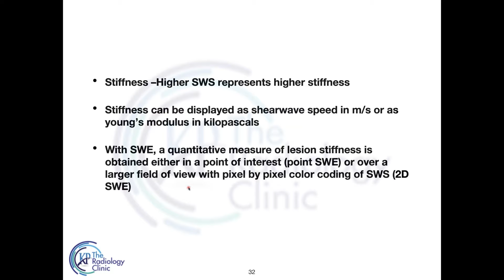With shear wave elastography, a quantitative measure of lesion stiffness is obtained either in point shear wave or over a larger field of view with pixel by pixel color coding of the shear wave speed. This is known as 2D shear wave. If we are using just the point of interest, then it is point shear wave. In point shear wave elastography, the region of interest, approximately 1 centimeter cube, is placed at the site of interest, and a single measurement of shear wave velocity is obtained from that location.